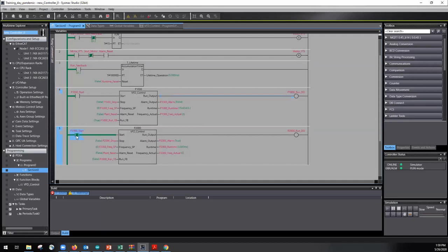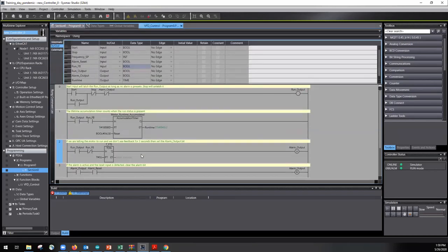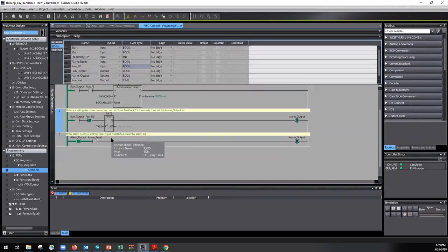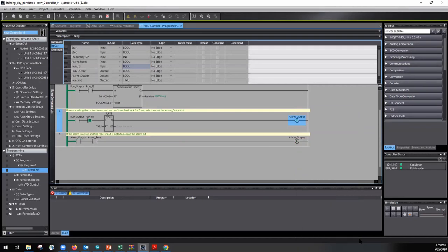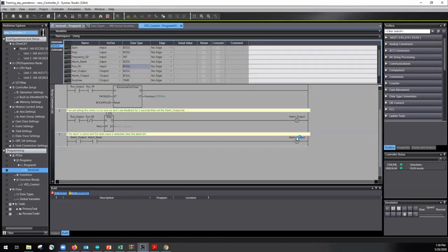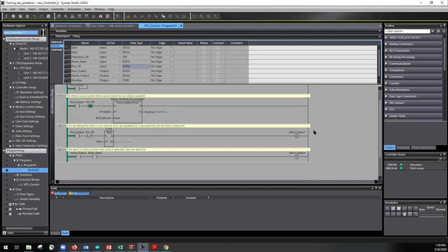So this one here, for example, I know that I've tripped the fail to start alarm. So I can go into it here, see the status of just this block. So there's my alarm. Oh, okay, very cool. So I can, just like ladder logic, reset it, and it's only going to affect that instance, the P2000 instance. P1000 is untouched because I wasn't looking in that one.